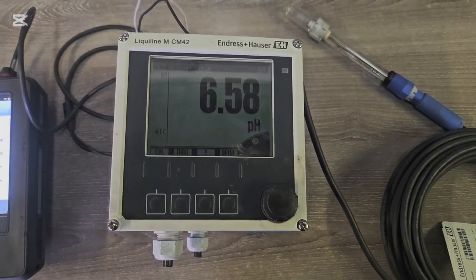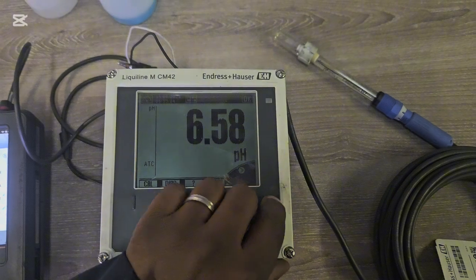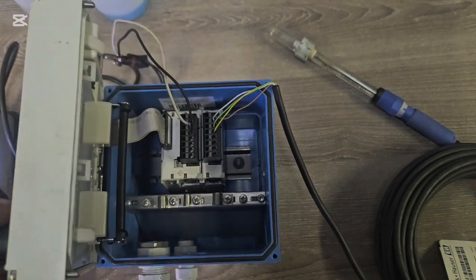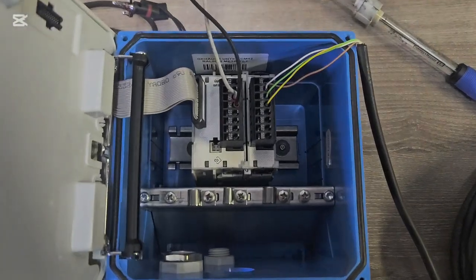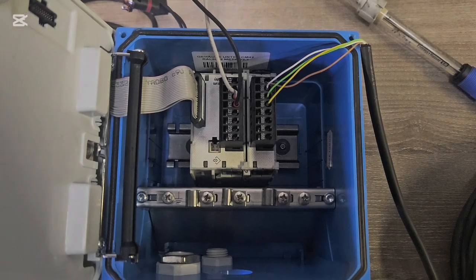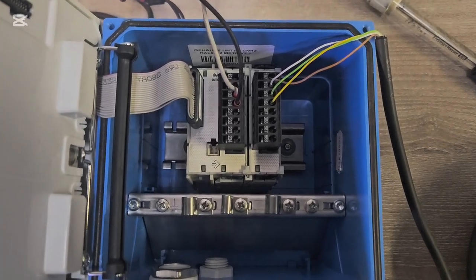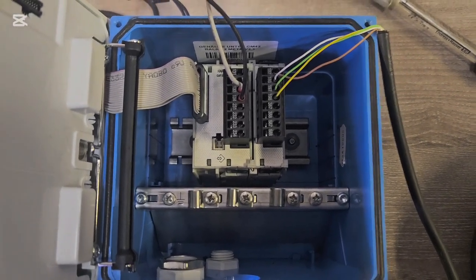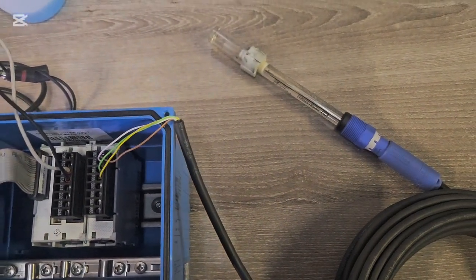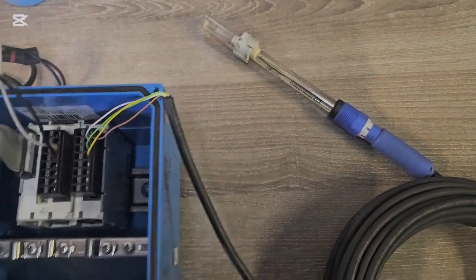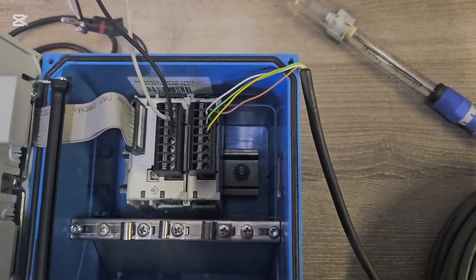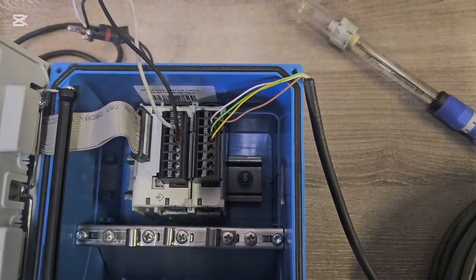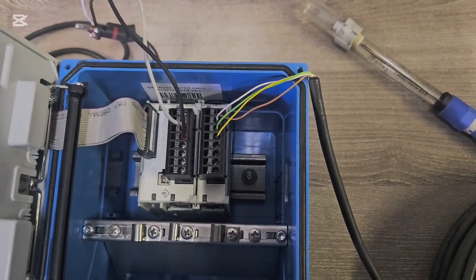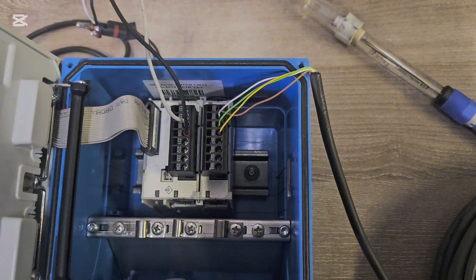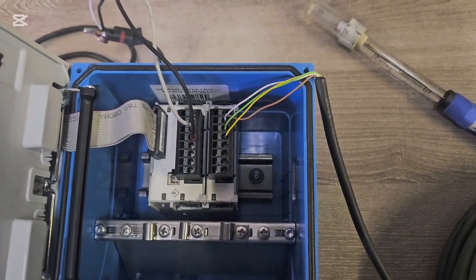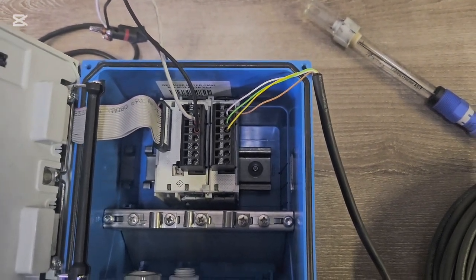So in the beginning, let's just look at the wiring. Inside the transmitter, you've got two cards. On the left is an amplifier card, and on the right is a sensor card. My pH probe this side has got four wires, and those four wires are connected to the card on the right. Two of them are supply, the positive and the negative, and the other two are the communication, which is the feedback from the sensor.